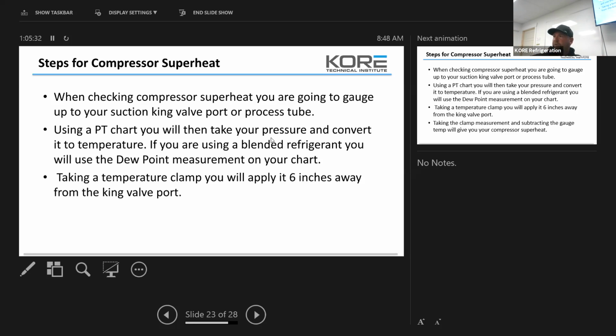If you're looking at bubble when you're doing superheat, you're going to be wrong. If you're looking at dew, because sometimes you're dealing with anywhere from a 6 degree to, I've seen it as high as 11 degrees on your glide. So obviously if you're dealing with an 11 degree glide, that's like a full state superheat setting temperature, right? You could be anywhere from a 9 to a 20 degree superheat if you're not looking at the right value. If you're at 20 degrees superheat because you're checking the wrong value at the wrong stage of the refrigerant, not only are you not going to capture enough refrigerant, but you're going to overheat the compressor. Because if your superheat's too high at the coil, you're not going to get enough cool gas back to the compressor. You're going to overheat it. You're going to take out that compressor. So again, we're dealing with finite adjustments here. Too little, overheat. Too much, you're going to flood it. So you have to make sure you're setting those properly.